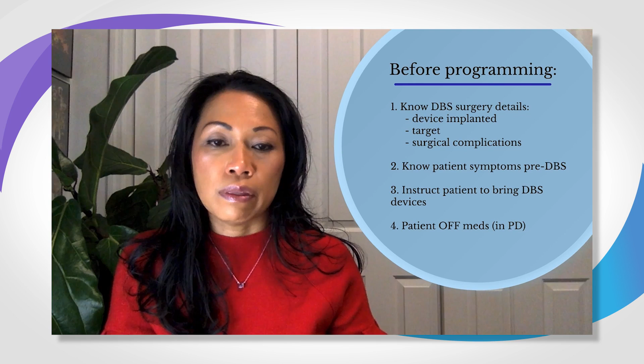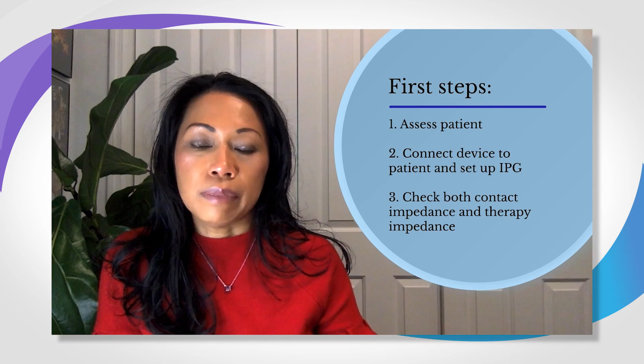So first thing we need to do is assess the patient. We need to know how they look, what their symptoms are, whether they have tremor, rigidity, bradykinesia, because those are the symptoms that we're going to be able to treat with deep brain stimulation. We need to connect to their device and make sure that their IPG, or implantable pulse generator, their battery, is set up and labeled as left STN or right STN, or left GPI or right GPI. We need to check both contact and therapy impedances. Why do we check impedances? It helps us to assess the integrity of the system, troubleshoot for device malfunction, and assess for current drain.